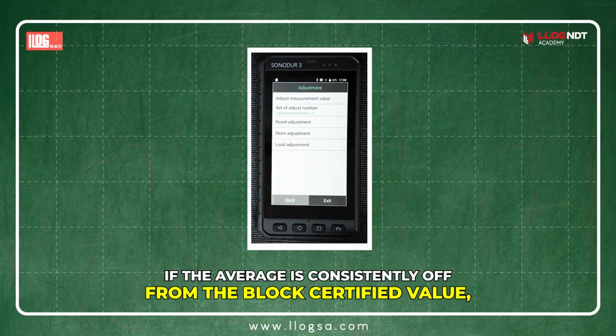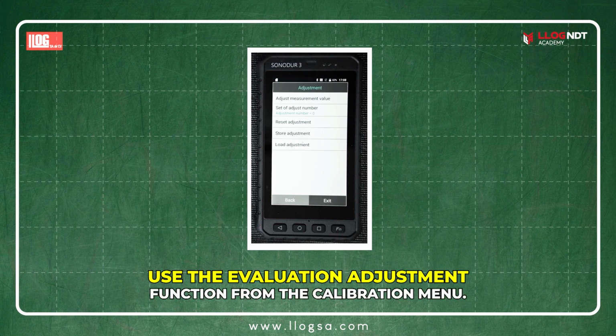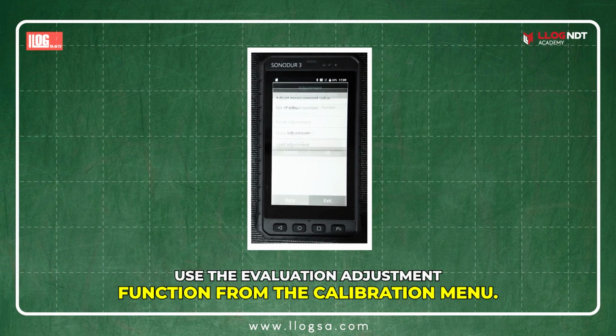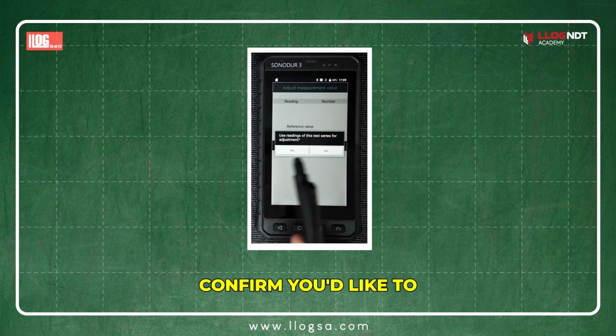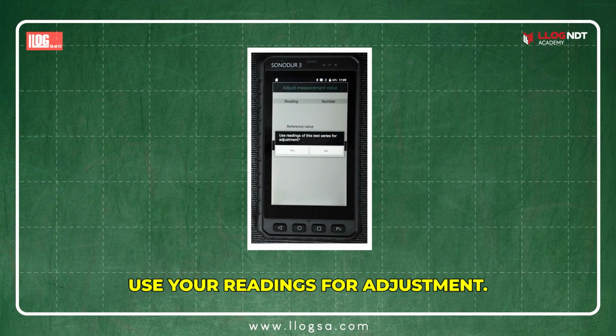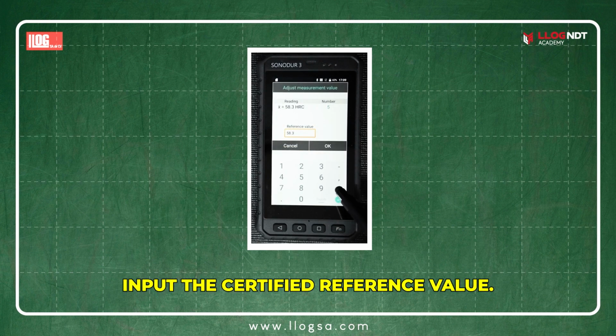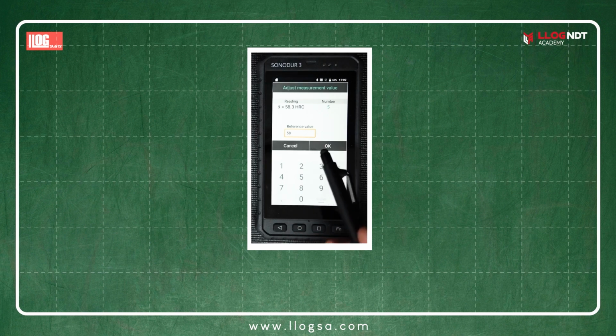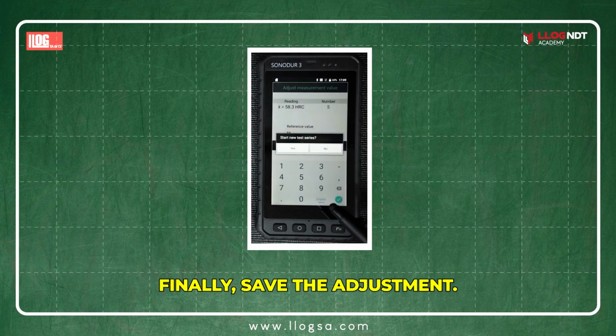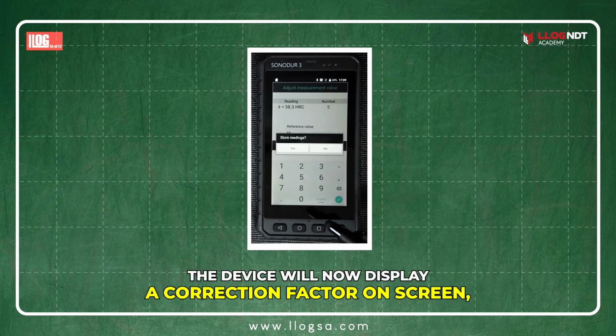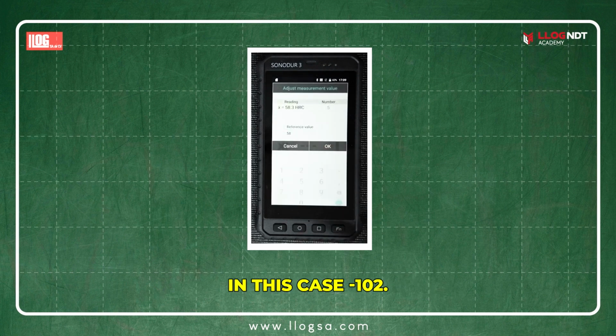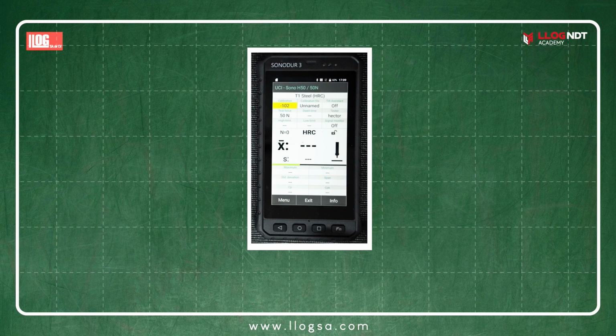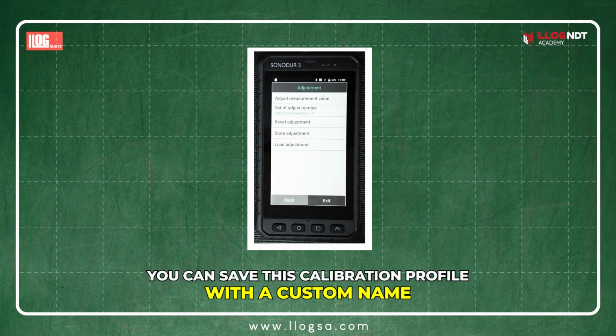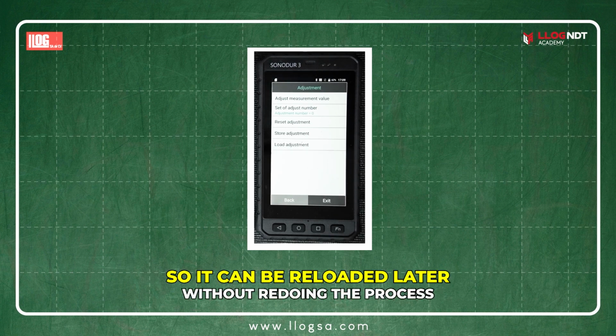If the average is consistently off from the block's certified value, use the evaluation adjustment function from the calibration menu. Confirm you'd like to use your readings for adjustment. Input the certified reference value. Finally, save the adjustment. The device will now display a correction factor on screen, in this case, -102. You can save this calibration profile with a custom name, so it can be reloaded later without redoing the process.